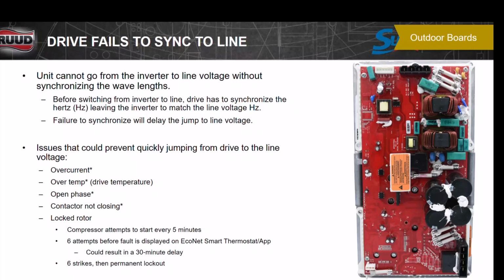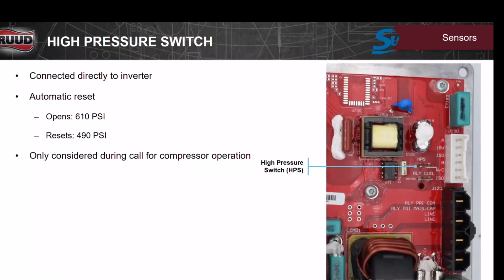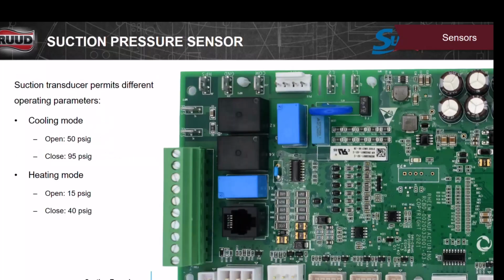There are protections in there against this happening. So if for some reason you have a blip in the voltage or something, it's going to kick the inverter out, and it's going to go into a time delay. So all that's in there. Connected directly to the inverter are the automatic reset high pressure switches and the suction transducer. This is what permits different operating ranges. So you're going to have the compressor going up and down. It's going to see the pressures in the system, so it's going to ramp the compressor up, ramp it down.